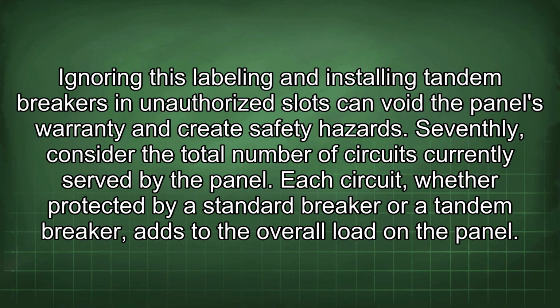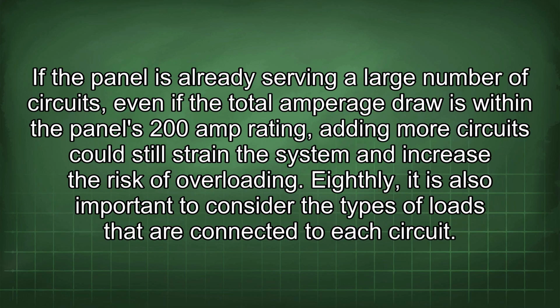safety hazards. Seventhly, consider the total number of circuits currently served by the panel. Each circuit, whether protected by a standard breaker or a tandem breaker, adds to the overall load on the panel. If the panel is already serving a large number of circuits, even if the total amperage draw is within the panel's 200 amp rating, adding more circuits could still strain the system and increase the risk of overloading.